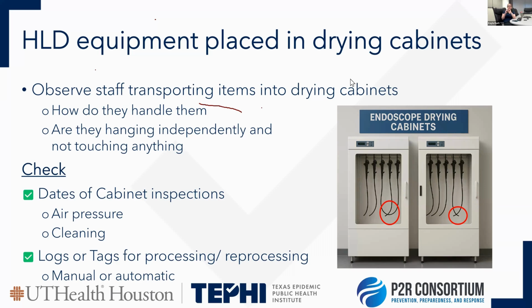And most of the time in these newer cabinets, there are specific valves that you can put in the channels that constantly circulate air through it to really help reduce that bioburden. So another thing you want to look at is that every specific endoscope has specific cabinets that go with it. Usually, whatever organization or manufacturer you're getting it from, they kind of put them together. So definitely look at what type of cabinets and how big your cabinets are based on your scopes. Your endoscopes or your duodenum scopes can be longer or shorter, and if you have ped scopes, making sure you have enough space where they're not touching each other is really, really important, and that they're being cleaned and serviced appropriately as well. Did that answer your question?